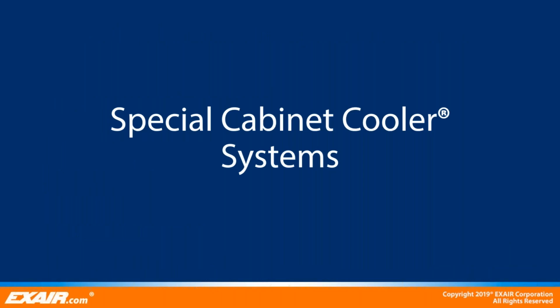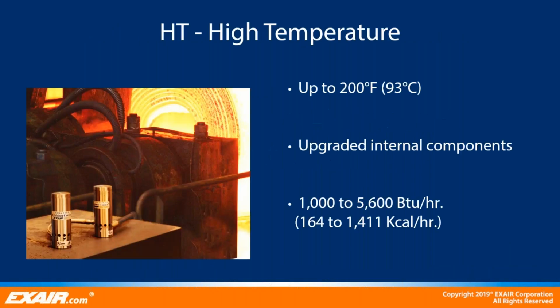EXAIR also offers special cabinet cooling solutions for even the most advanced and complex applications. Better yet, they are all stock items as well. Special high temperature cabinet cooling systems are available for areas where ambient temperatures range from 125 degrees Fahrenheit to 200 degrees Fahrenheit. Upgraded internal components are able to withstand higher temperatures, like those near boilers, ovens, furnaces, just to name a few. We offer systems ranging as low as 1,000 BTU per hour up to our largest dual system, providing 5,600 BTU per hour of cooling.